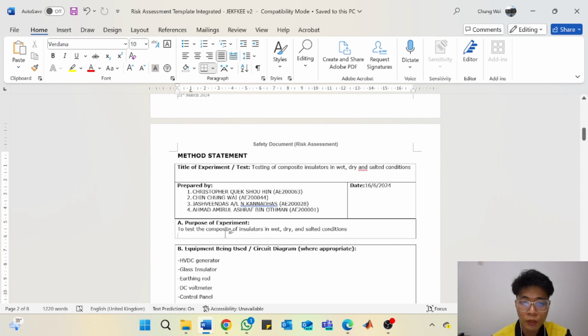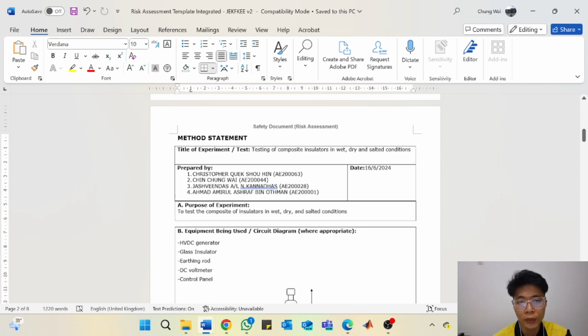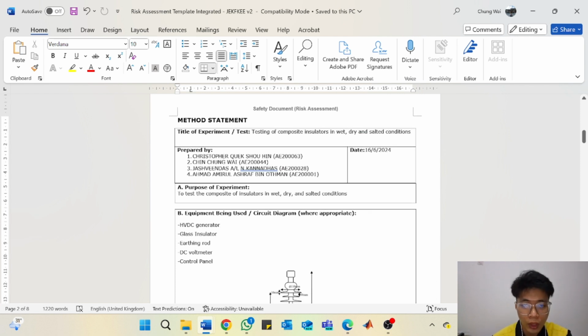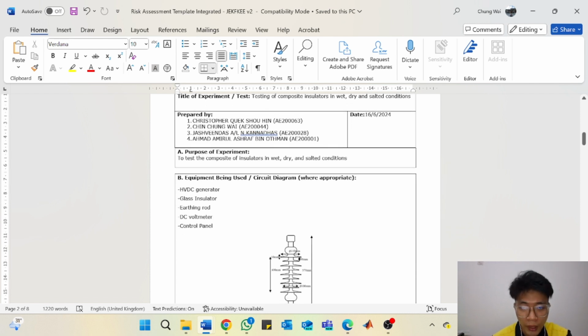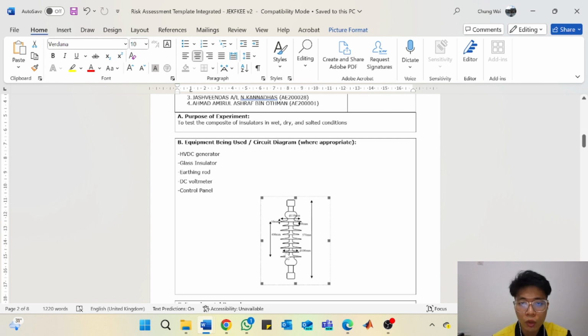So the purpose of this experiment is to test the composite of the insulator in wet, dry, and also salt condition. The equipment that are being used are the high voltage DC generator, glass insulator, earthing rod, DC voltmeter, and control panel. This figure shows our proposed polymer insulator.